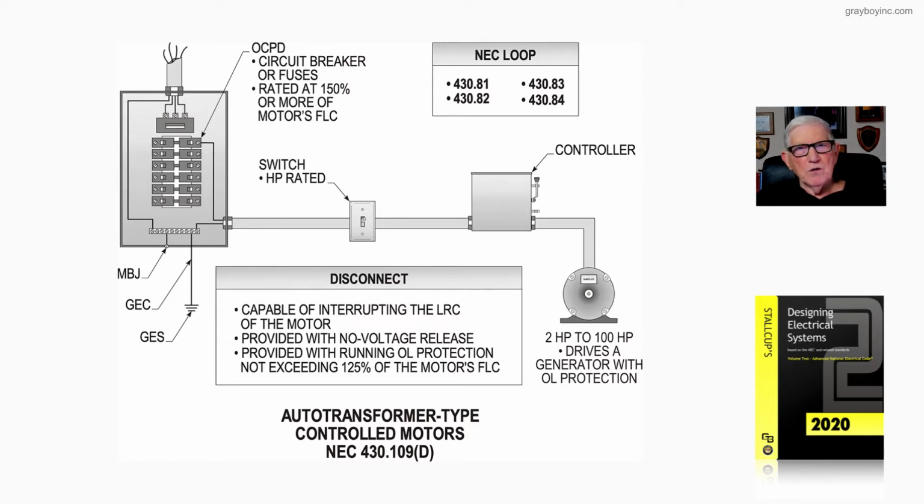What type of motor do you have? What is the phases of the motor? What is the code letter of the motor? And then select your devices. In this case, it's fuses or circuit breakers. It's 150% is what we would find.